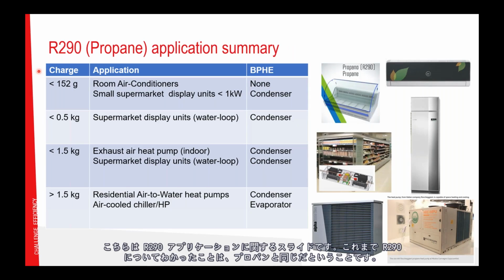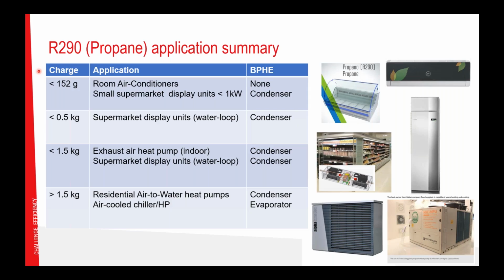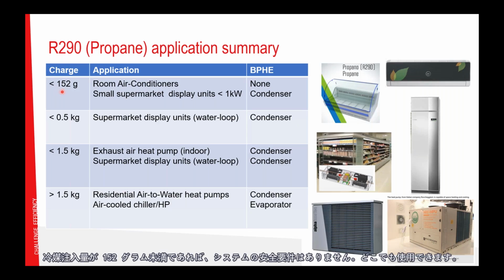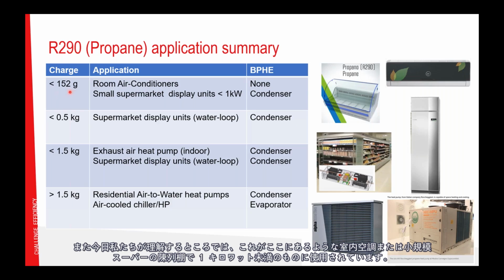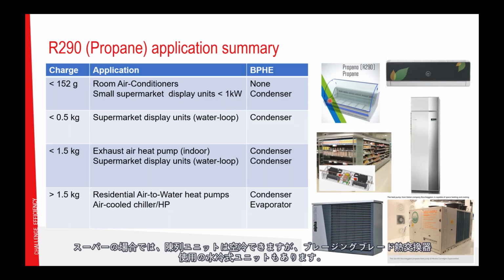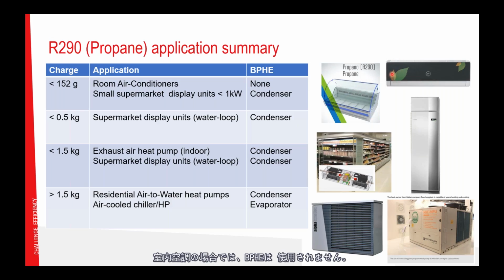Here is a slide on R290 applications, what we have seen so far. And R290 is the same as propane. And it's very much related to the charge of the system. If the refrigerant charge is below 152 grams, there are no safety requirements in the system. You can use it everywhere. And what we see today, it's being used for room air conditioners, like this one here, or in small supermarket display units below 1 kilowatt. And for the supermarket display units, they can be air-cooled, but we also see water-cooled units where a brazed plate heat exchanger is used. In the case of room air conditioners, there is no BPHE used.